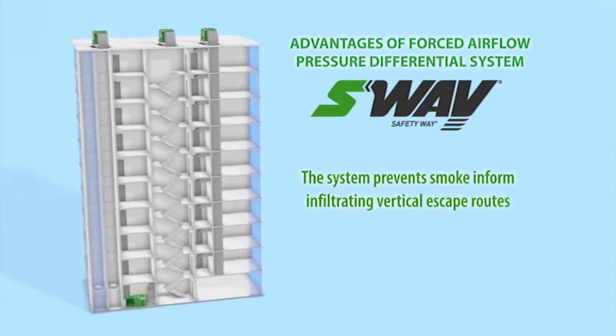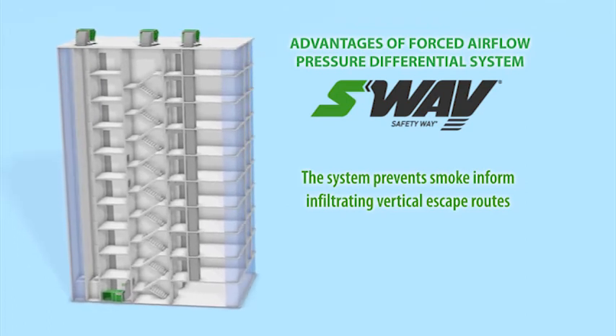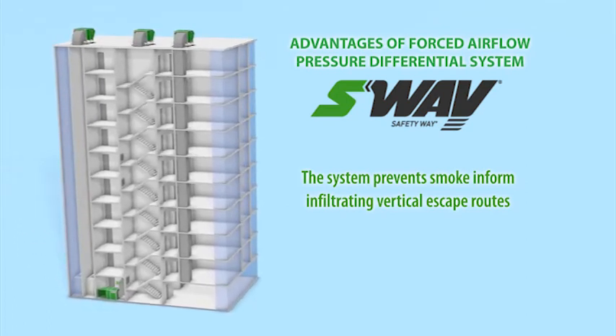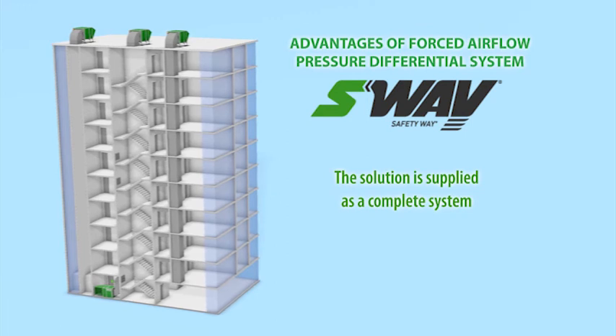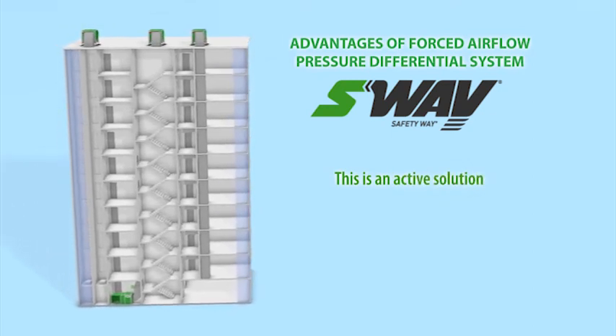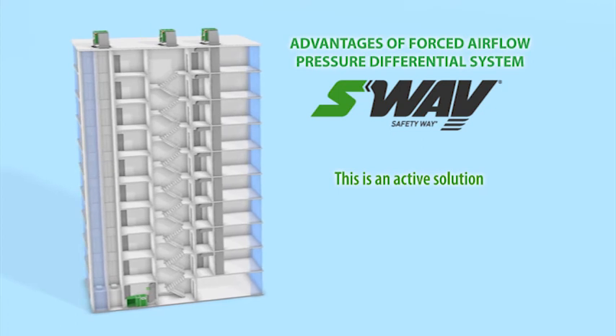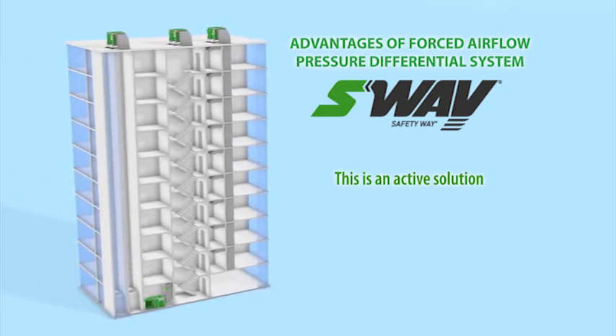The system prevents smoke from infiltrating vertical escape routes in the event of a fire in residential, office and industrial buildings, regardless of how tall they are, the time of year, temperature differences or wind forces. The solution is supplied as a complete system optimized for use in a given building. This is an active solution, allowing for simple adjustments of settings, monitoring the current operational parameters, as well as automatic adjustment to rapidly changing parameters such as air temperature or wind.